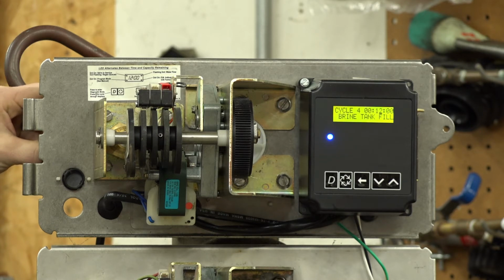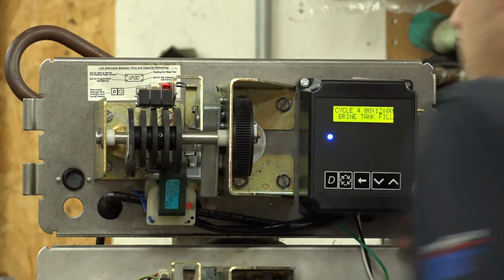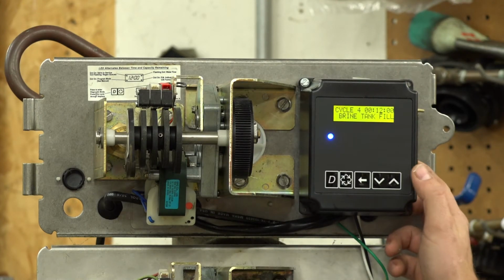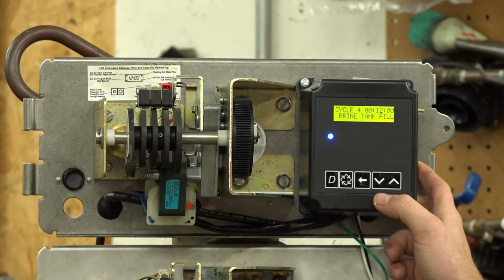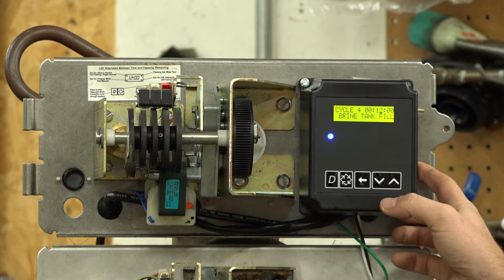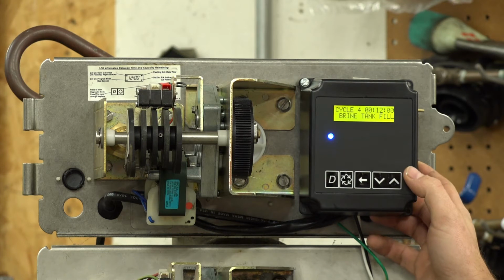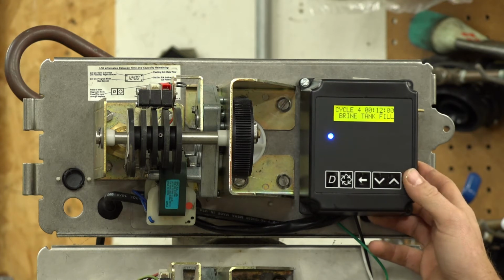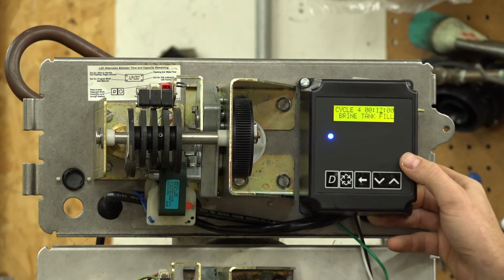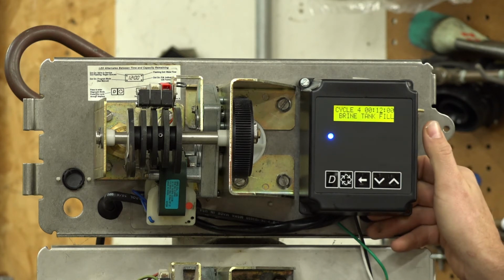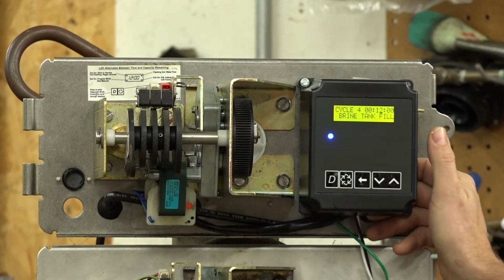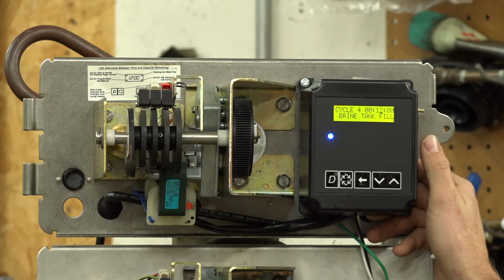The other place that it will be located is in the brine tank on the safety float. So just identify your brine line flow control. That way you can calculate, based on your capacity and resin, how much time you need to fill. An example of that is if you had a 5-gallon minute refill flow control and you needed 15 pounds of salt per cubic foot, you're going to need to calculate that out to make sure that you have the proper quantity of brine in the brine tank for regeneration.